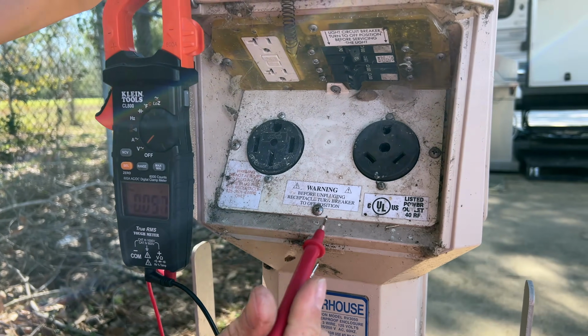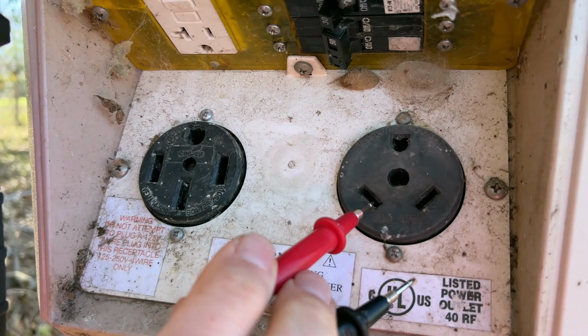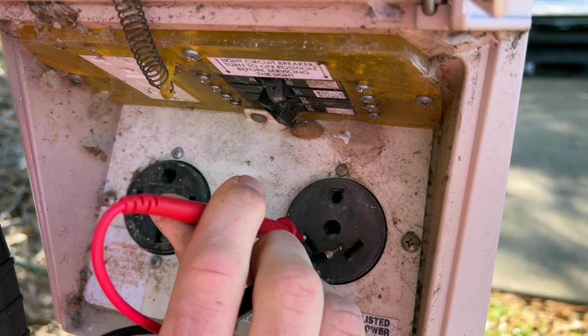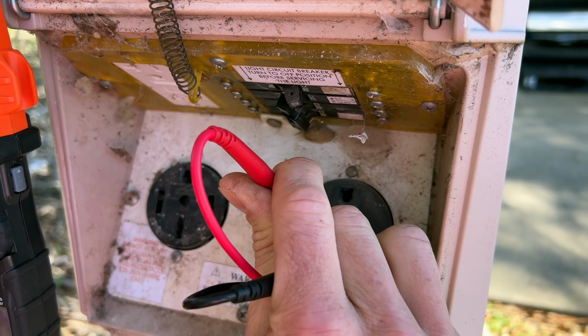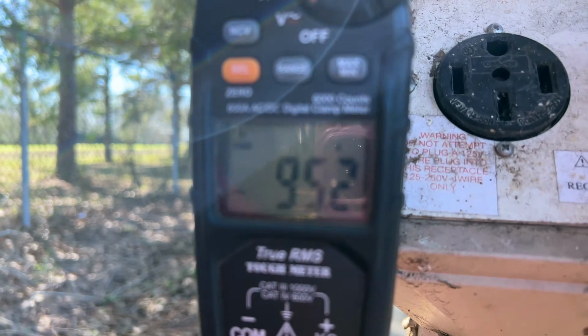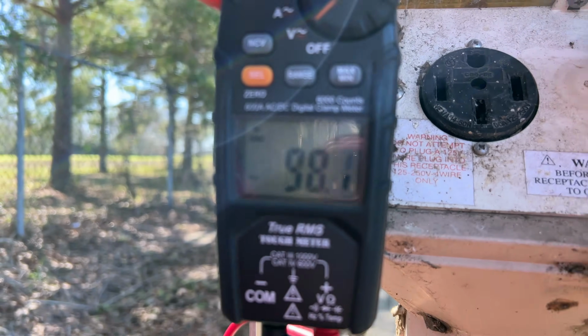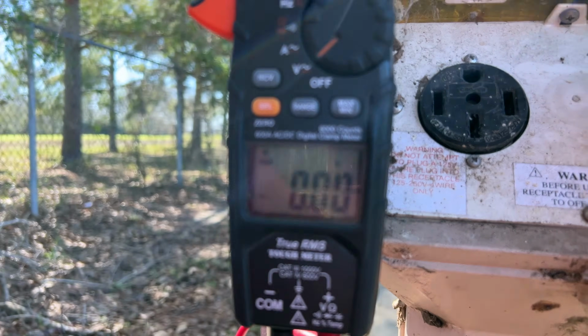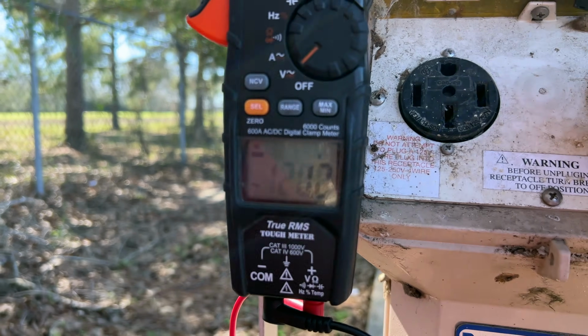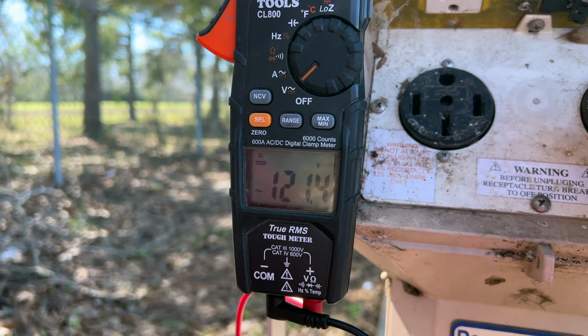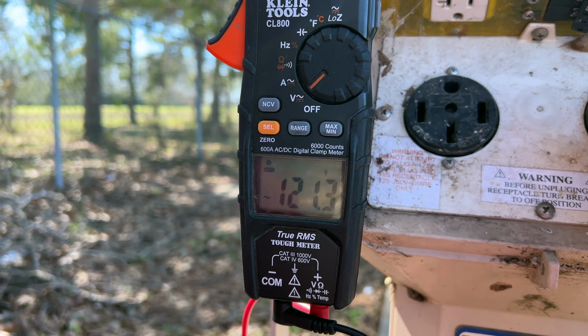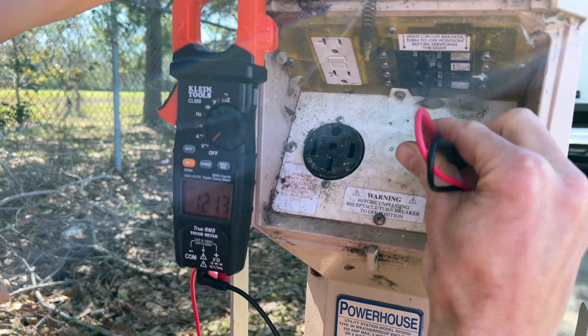So I'm going to take the red lead, put it into the left hot slot, and put the black lead into the right neutral slot, and read our meter. We should be around 120 volts. Sometimes, if you don't quite get there, that means you're not touching the metal properly, so wiggle it around, make sure you're touching the metal securely inside of the plug. So that's reading good voltage.